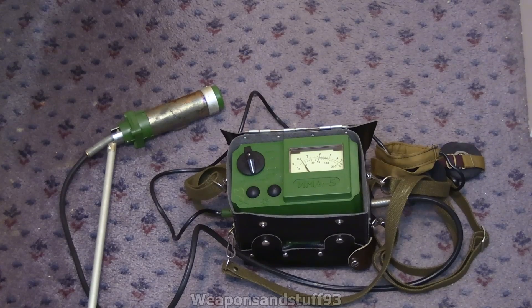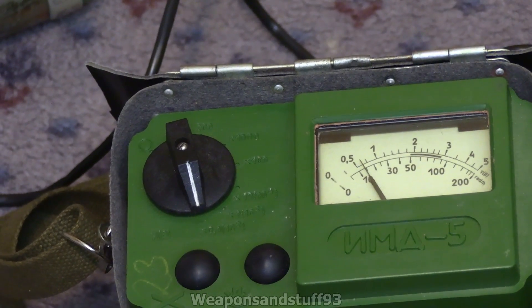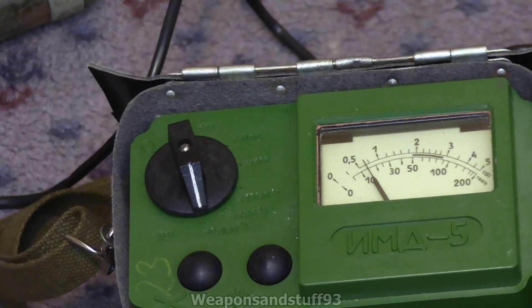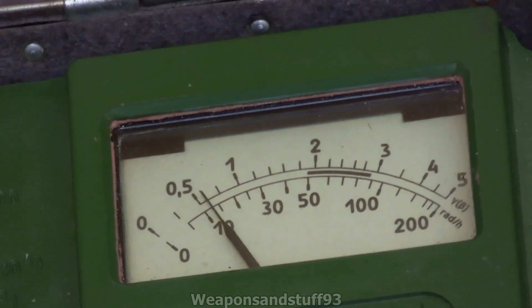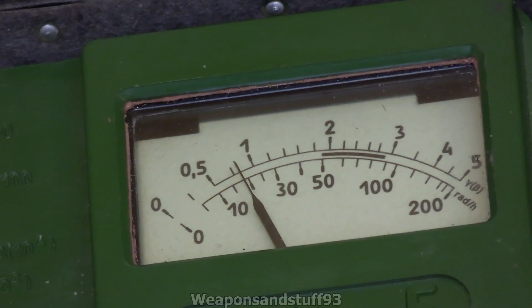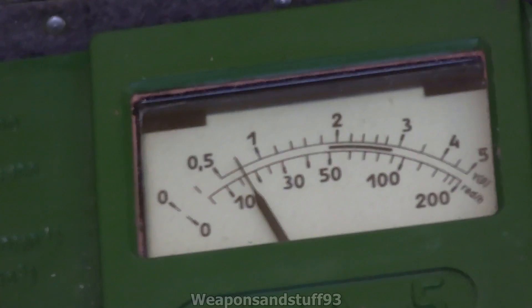Here's the IMD-5 itself. It uses the exact same range selection switch as the DP-5 — it's just chunkier and easier to use. Here is your control panel: you have off and battery test at the top, then you've got all the ranges starting at 0.1 and going up to 200. On the 0.1 setting you read the top scale and put an extra decimal point in, so where it's between 0.5 and 1, that's actually 0.05 to 0.1 milliroentgen per hour.